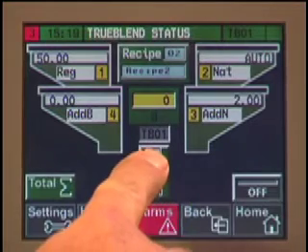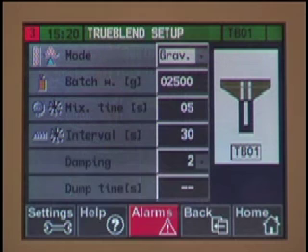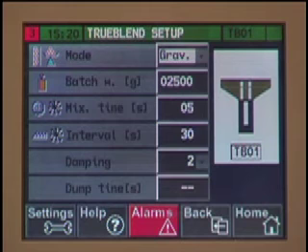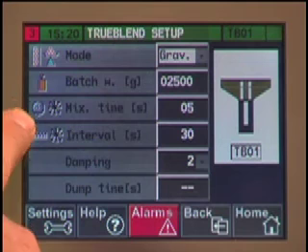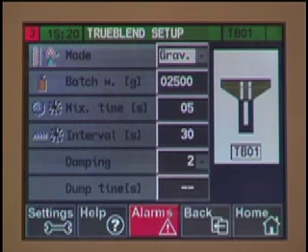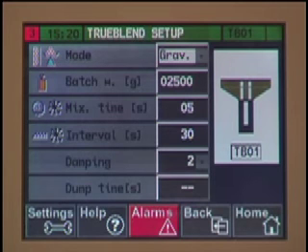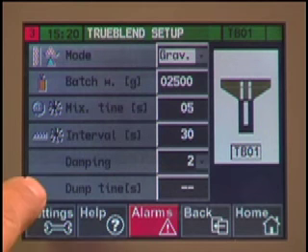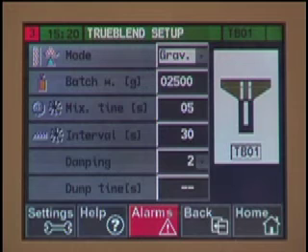Next, we will enter the True Blend setup screen. The following selections are available: mode — selects blender operating mode; batch weight — sets the weigh bin target weight, which by default equals the model number times 10 grams; mix time — sets mixer run times after a batch is dispensed; interval — sets the time between motor jogs after mixing time has expired; damping — the vibration sensitivity level setting; and dump time — sets the time that the discharge valve remains open for material dump. These are all factory preset for optimal performance. The only two that may need to be adjusted are mode and batch weight.